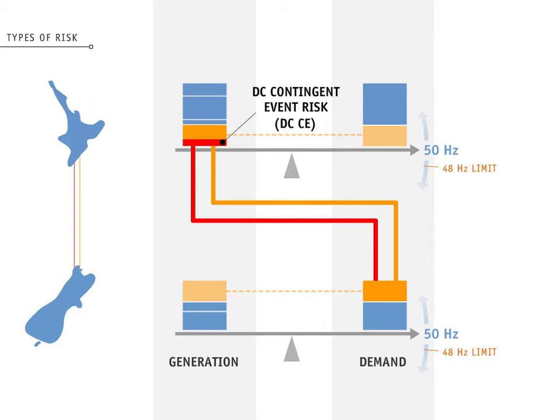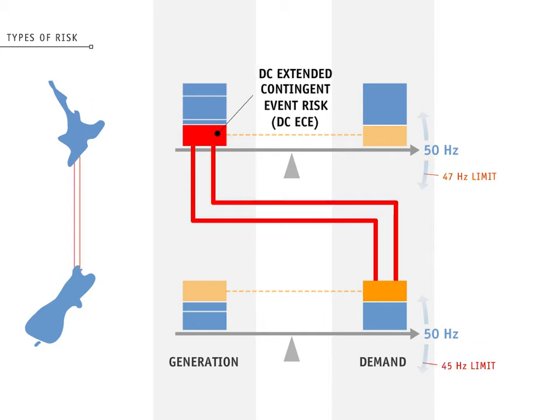The DC-CE risk is calculated as the total HVDC megawatts received, minus the lower overload capability of the two poles. A DC extended contingent event, or DC-ECE, is defined as losing the total megawatts received over the HVDC link. If a DC-ECE happens, the loss of the HVDC link will sever transmission between the North and South Islands.